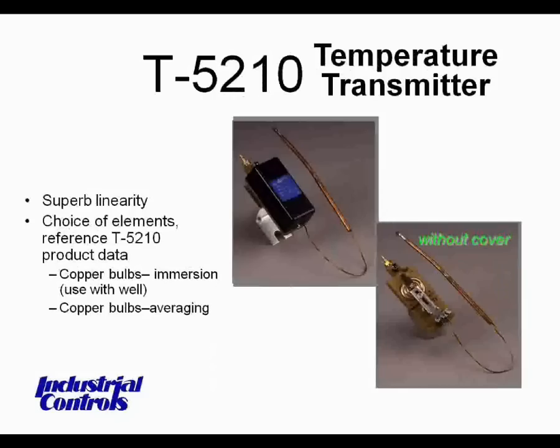Two things: looking at the picture without the cover, the round circle that looks almost like a silver dollar made out of brass — that's the temperature-sensitive element. That represents a bellows that expands and contracts, much like a bimetal, but it's not a bimetal. Averaging elements, as discussed, can be up to 20 feet long, and are meant to be spread across a coil or ductwork to allow for stratification.